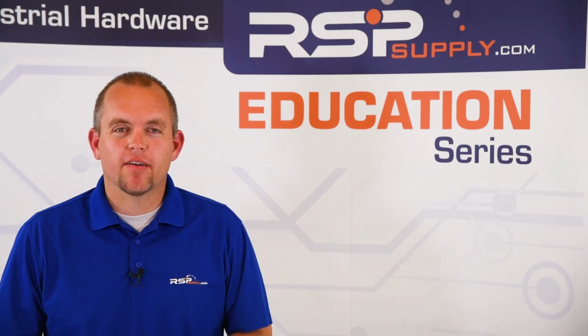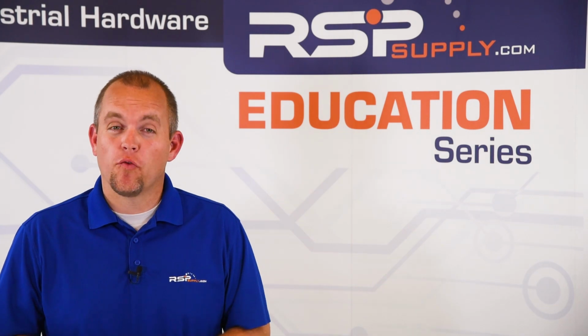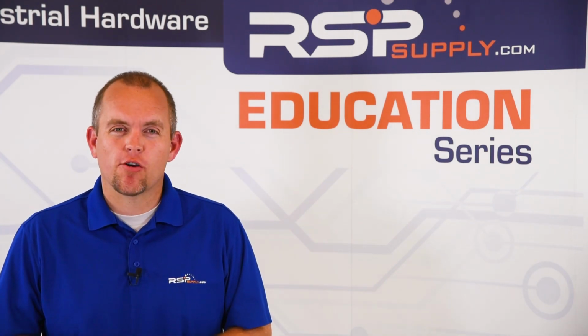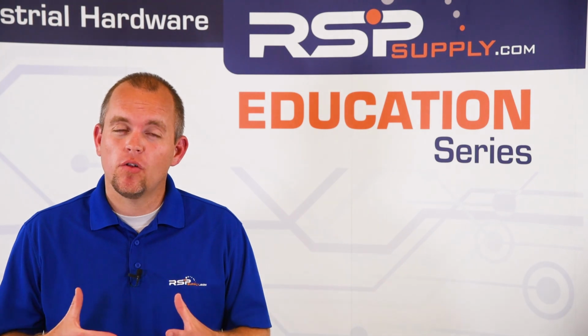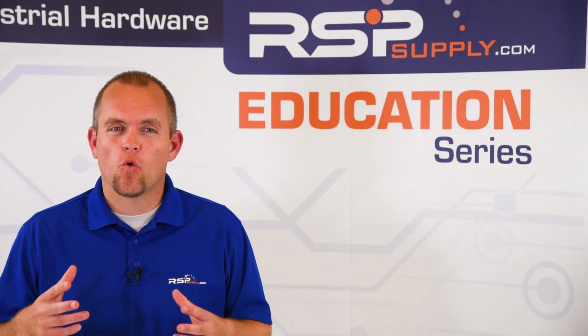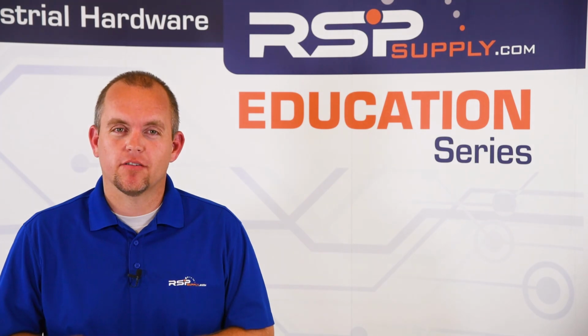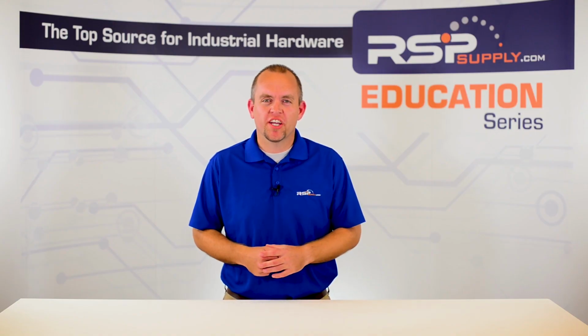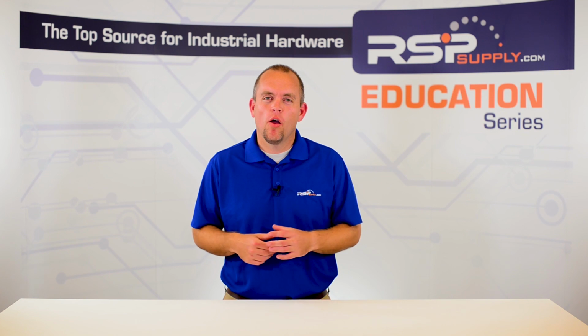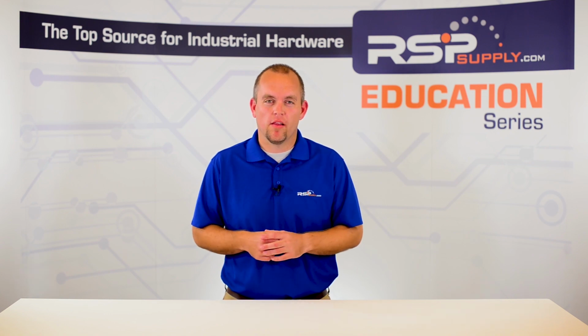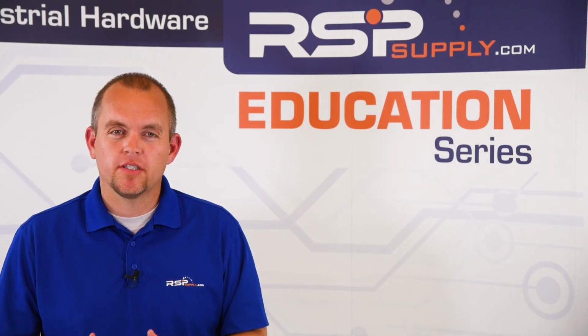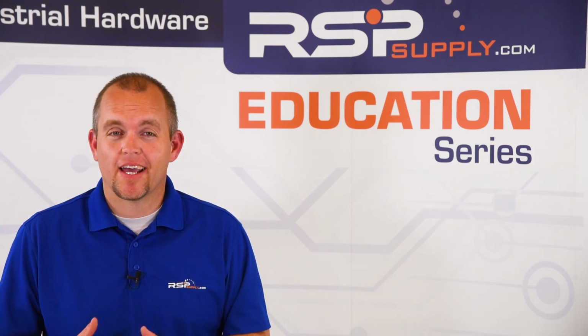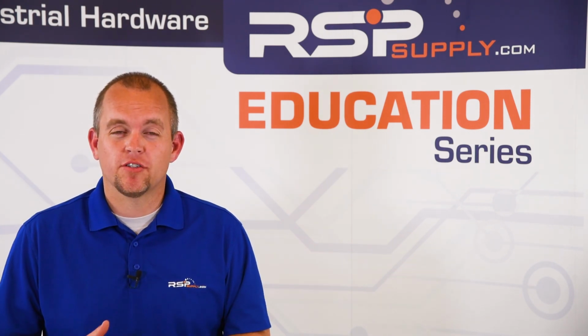Analog signals can take many different forms. Some of the more common are a 4 to 20 milliamp signal, or a 0 to 5 or 0 to 10 volt signal, or there are many other voltage or amperage variations with analog signals. Due to interference and noise, which can affect significantly long runs of wire, we want to make sure with analog signals that we use a twisted and shielded pair. This will help us reduce that interference and noise with analog signals. In comparison with analog signals, digital signals are much easier to sense and create, therefore the hardware related to these types of signals is significantly reduced.